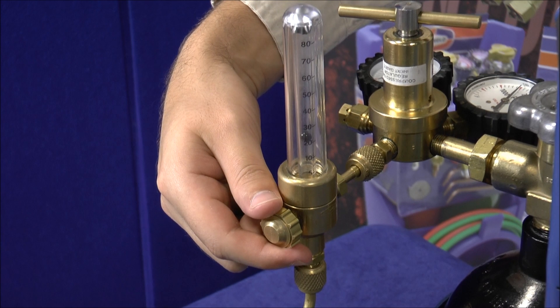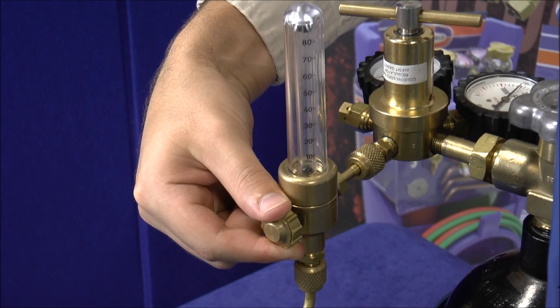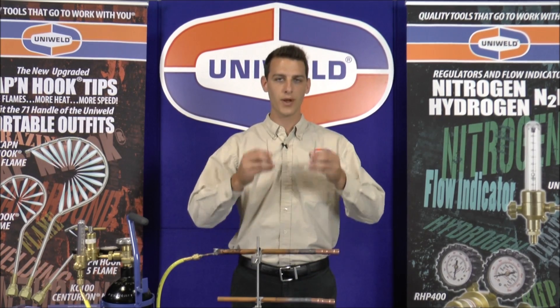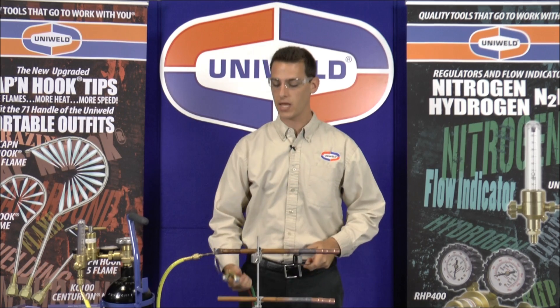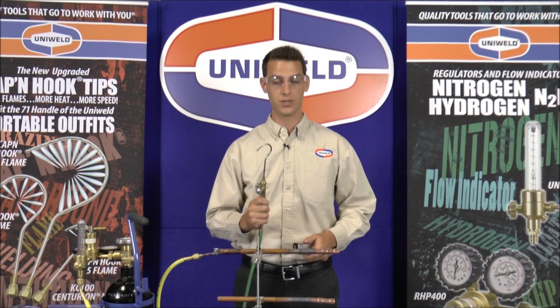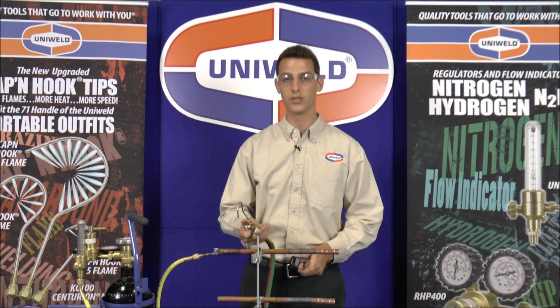Once I have purged the lines of any air I will dial back the flow of nitrogen to 3 CFH. Now I'll go ahead and braze these two joints. I'm using Uniweld's Oxy-Acetylene Outfit and our MTF5 Cap'n Hook Tip. This is a five-flame tip that directs all the heat onto the copper and provides a 100% wraparound on the tubing.